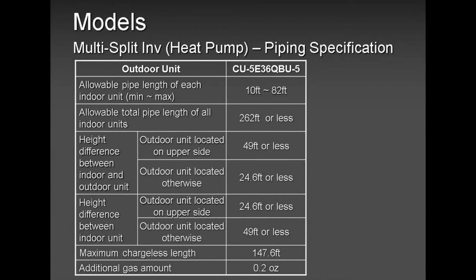Again, if you're not sure, and if you get a job 2-3 months down the road, remember to call us, to ask us. There is no harm in asking. Because if you're going to bring half inch and quarter, 20, 30 feet all the way down to the outdoor unit, and then downsize it to 3/8 and quarter, you will have problems with refrigerant. The diameter is a bit larger, and eventually the system is going to tell you, you are low on gas because of the diameter of the pipe. So once again, I am repeating, 3/8 and quarter is at the outdoor unit.